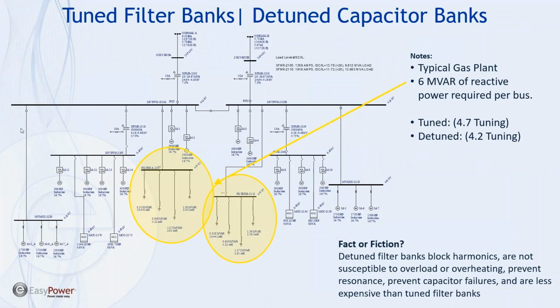So the first myth we're going to talk about is detuned harmonic filter banks. It's often thought that if you purchase a detuned filter bank, you don't need to worry about harmonic overload within the filter itself. You don't need to worry about overheating. You don't need to worry about resonance concerns or capacitor failures, and that they're less expensive than tuned filters. So we're going to talk about the difference between 4.7 tuning and 4.2 tuning and some of the myths that surround this. So what you're looking at here is a gas plant.